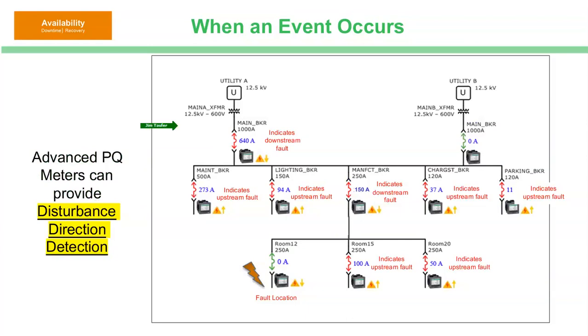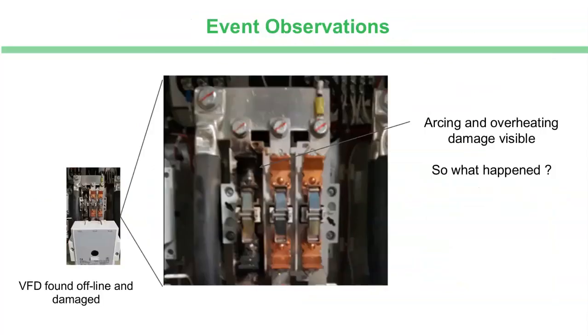So we can see here at the main, there we go, that there was a fault and it was downstream. And we see from the feeders that they were seeing it upstream, except this one right here. And follow it, and you can see the fault location is pointed to, so that immediately all of the technicians and those that are responding know that something's occurred, and they know where it occurred, and they know which direction it came from. So that was a real event, and this is what they found.